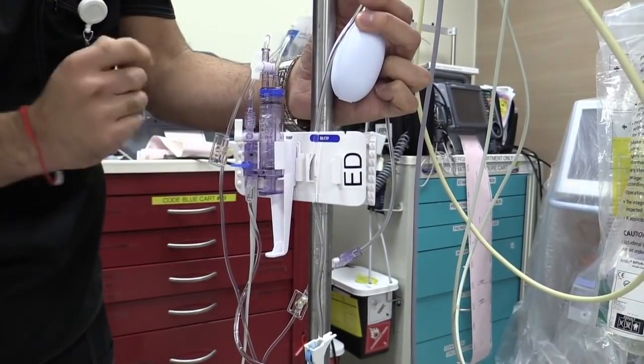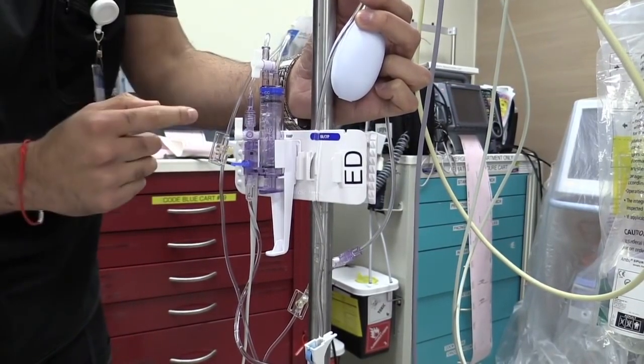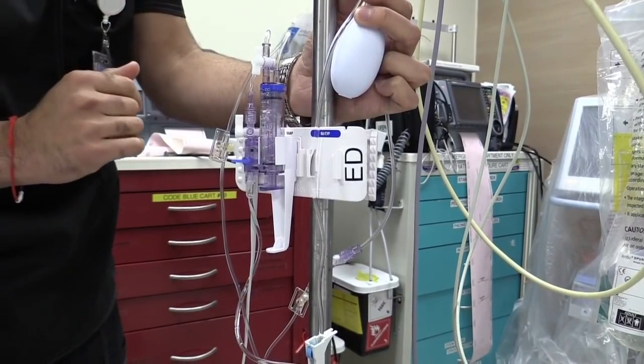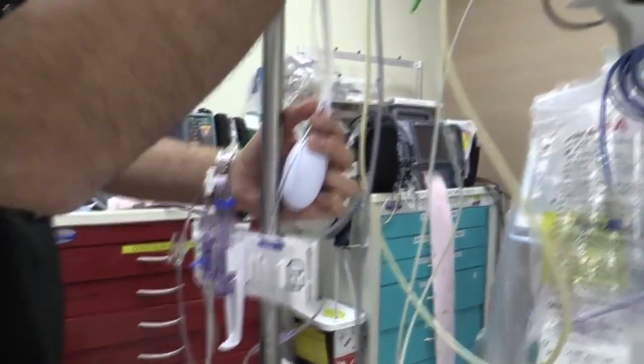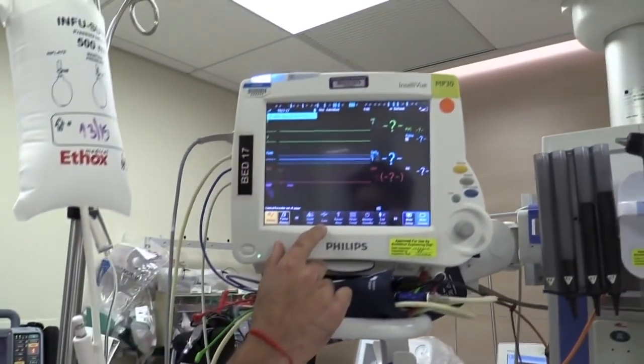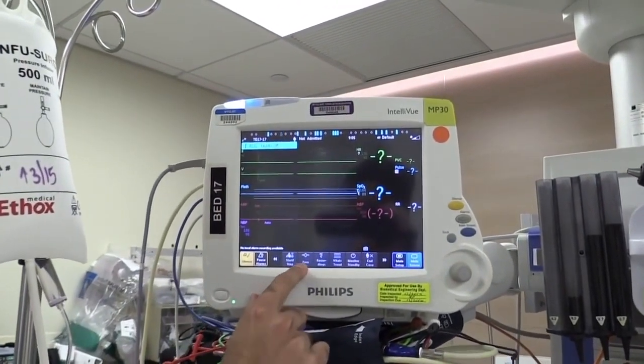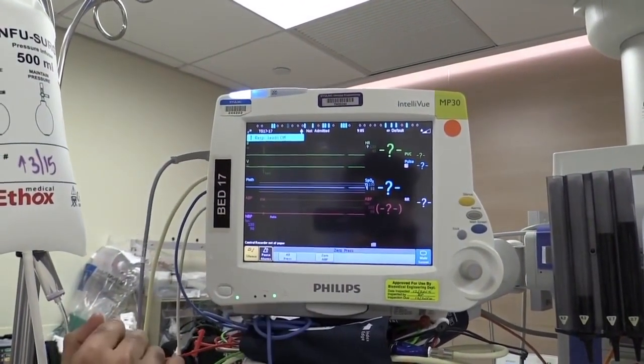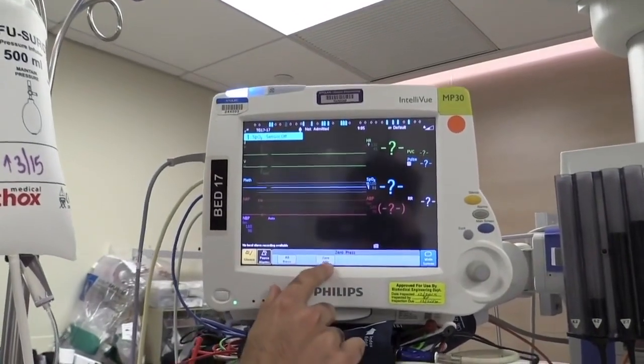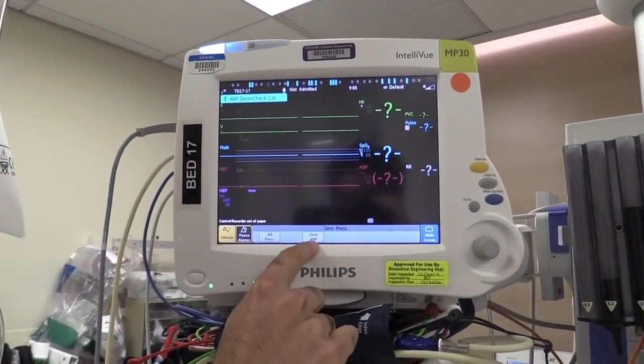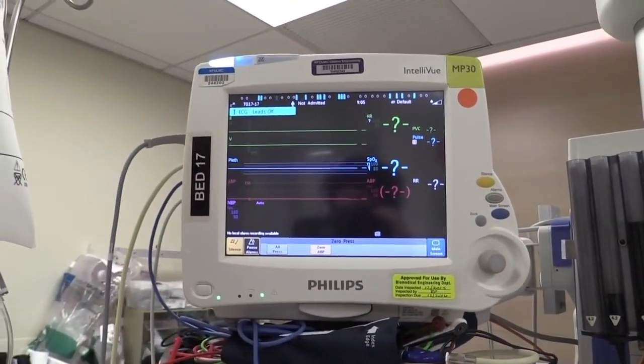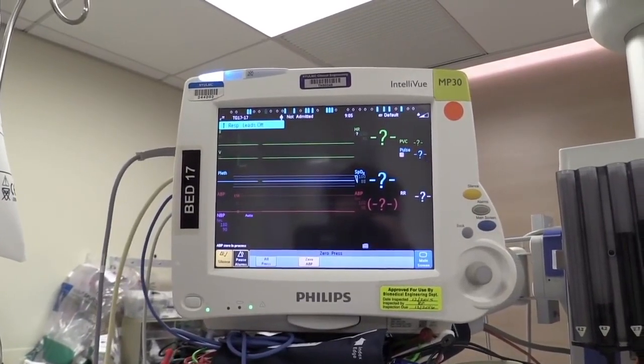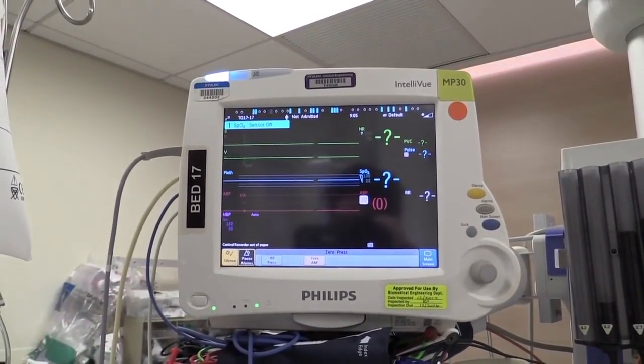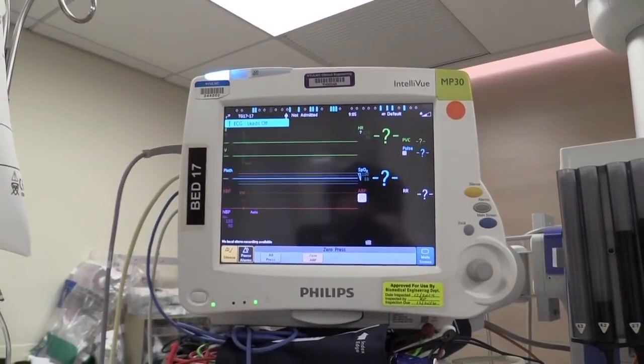So as soon as you're exposed to the atmosphere, you have to tell the computer that this is what I want zero to be. So we're going to come back up here, Brian, and we're going to take a look at the screen, and there's a button here that says 0. All you're going to do is press the 0 button, and two more options pop up, and you press 0 ABP or 0 arterial blood pressure. You're going to press that again, and essentially that is zeroing it for you. Perfect, and we're right at 0.